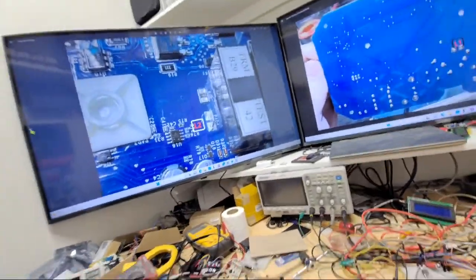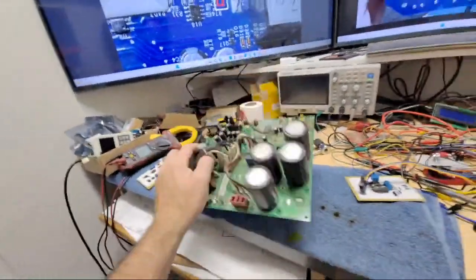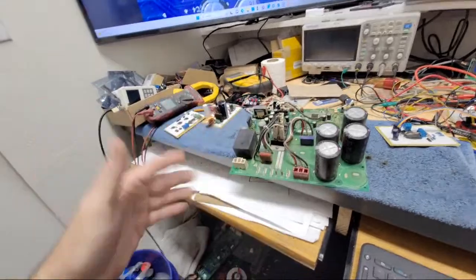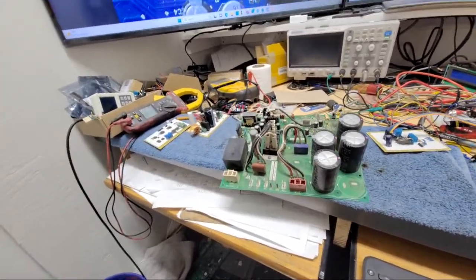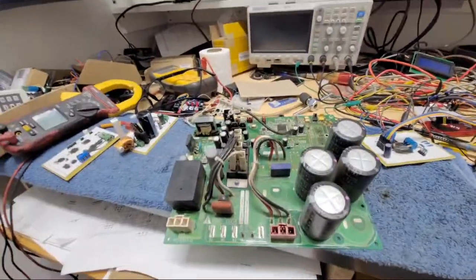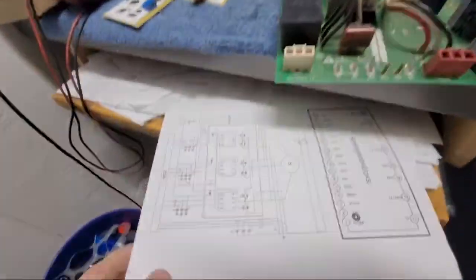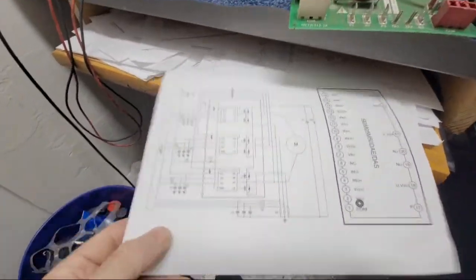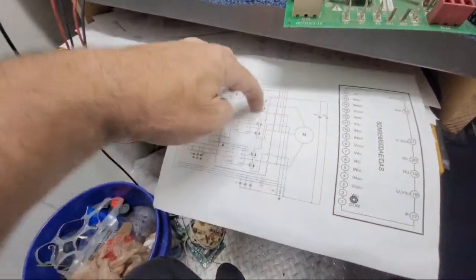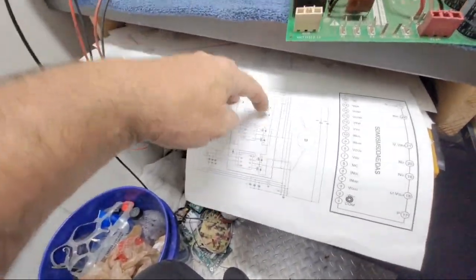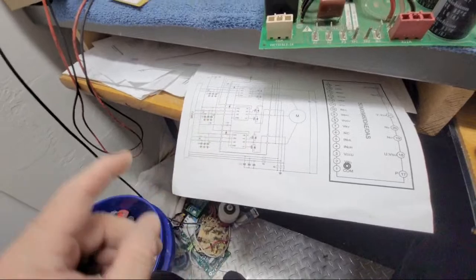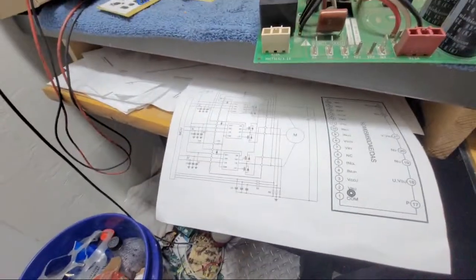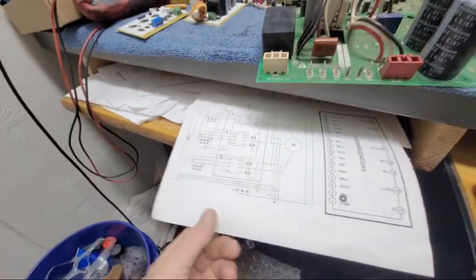And I brought in a board - of course this is a blown up one. This isn't a variable frequency drive, this is an IPM, inverter power module, for a brushless DC compressor, which would be one of these circuits basically. So you have 3 pairs, think of it as 3-phase, and you'd do it like a 3-phase VFD similarly. It's just the way it's done.